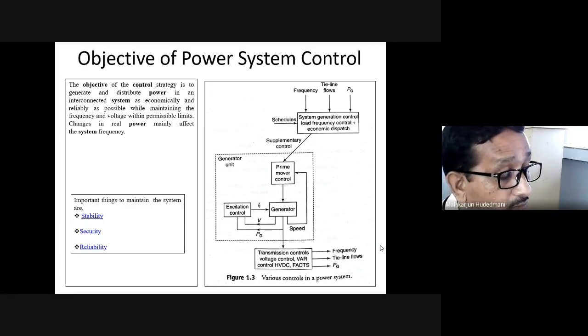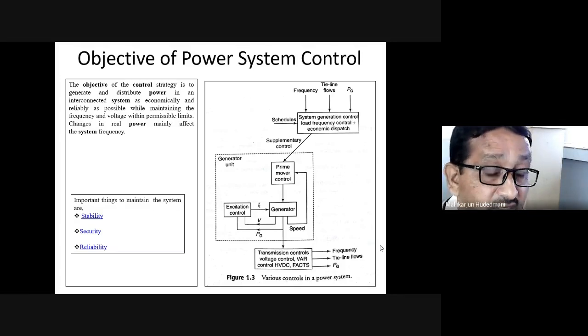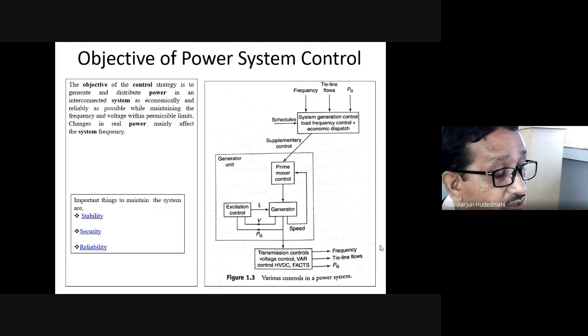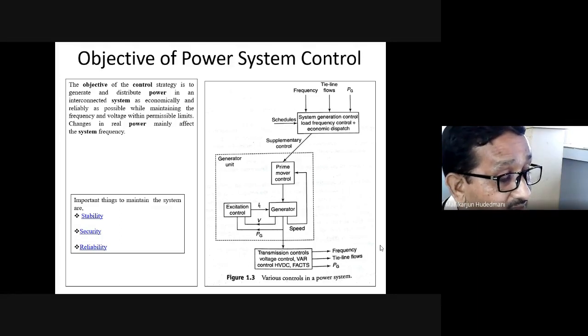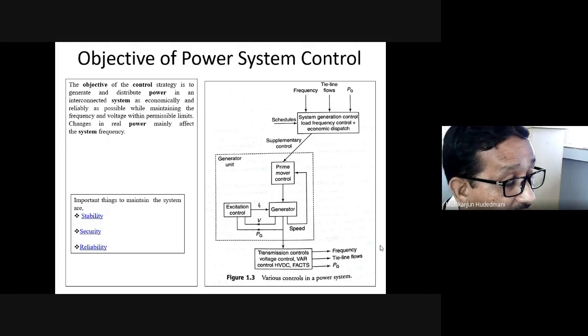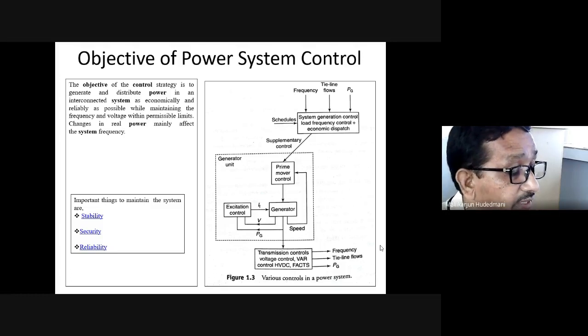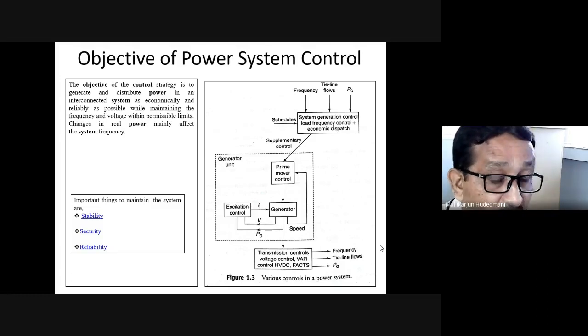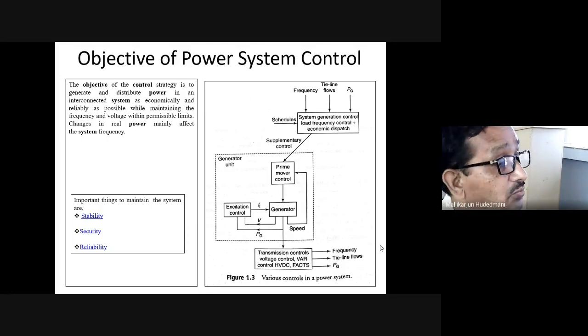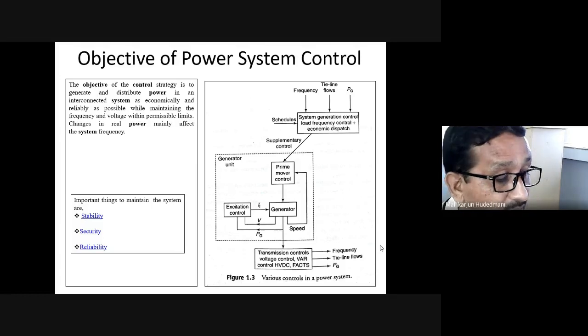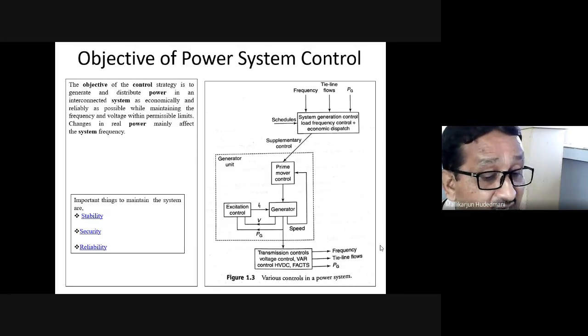Surely they encounter overtravel, overload, and contingent changes in their delivery pattern, during which do the component or the connected system is safe to operate, remain in operation even after encountering that difficulty or defect, or is it safe to isolate it? Such kind of aspects, when we look forward, that come under security. It is most important aspect of the operation of the power system, because when the objective which is put to generate adequate active and reactive power and deliver to the end user reliably, it is definite to that system is open for such challenges at every moment of its operation.